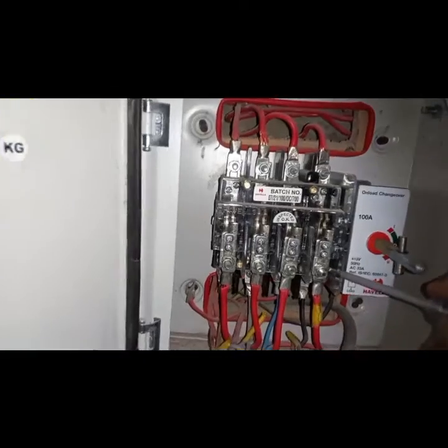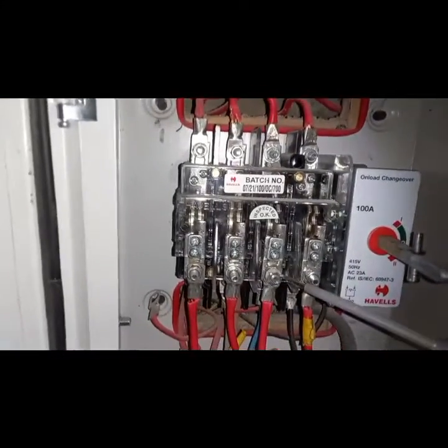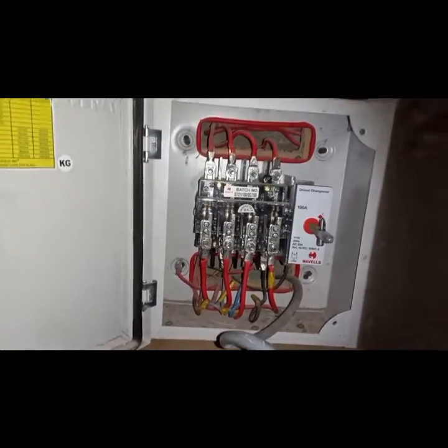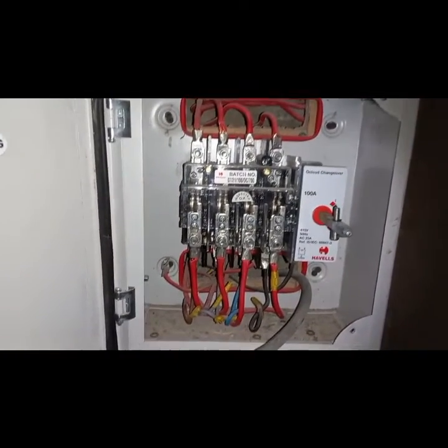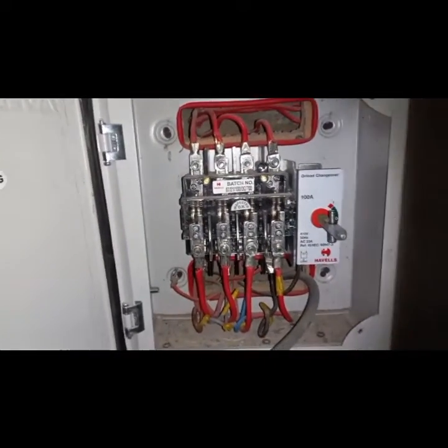Always note that this side up here, the one right in front of you, is the load — meaning this is the one that will send supply or power to the various distribution boards that you have. Unless you've switched it to one of the power sources, this one will not receive any supply. I think this is clear now, because I've been receiving a bunch of calls on this particular subject.